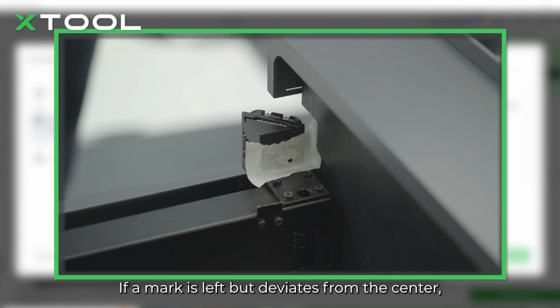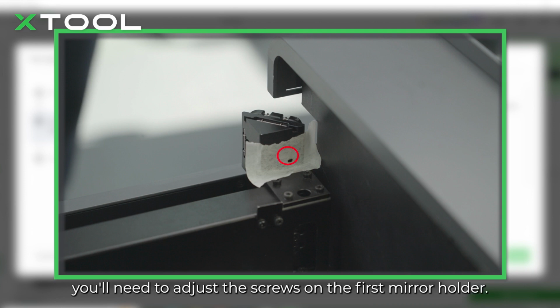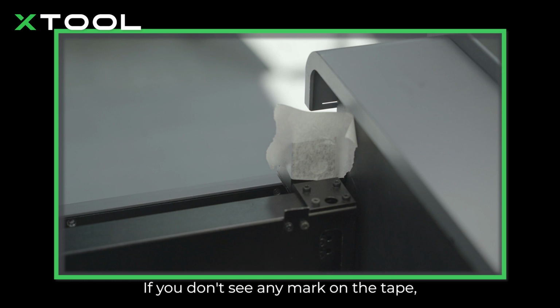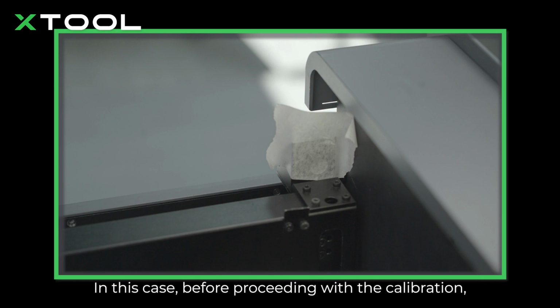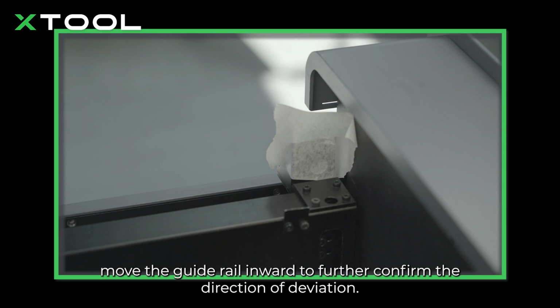If a mark is left but deviates from the center, you'll need to adjust the screws on the first mirror holder. If you don't see any mark on the tape, try clicking Pulse a few more times. If still no mark left, it indicates a serious deviation in the path. In this case, before proceeding with the calibration, move the guide rail inward to further confirm the direction of deviation.